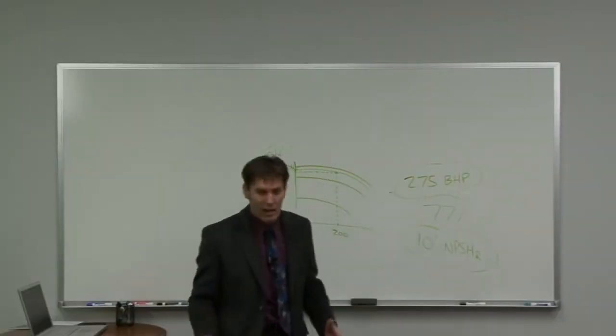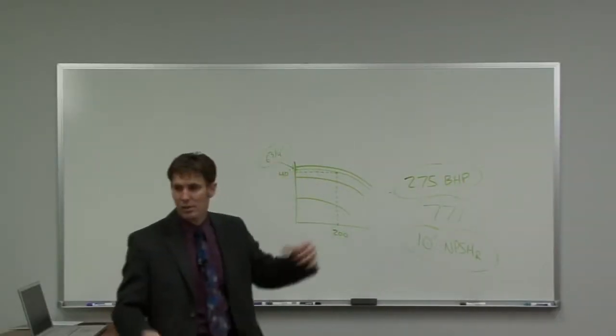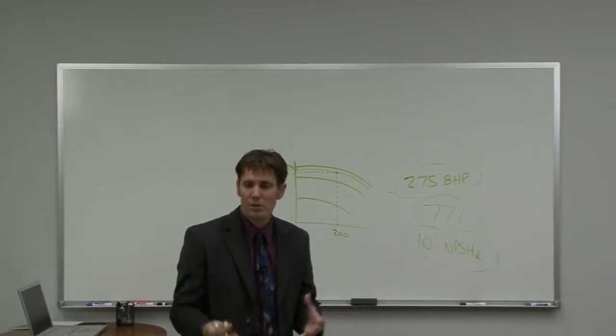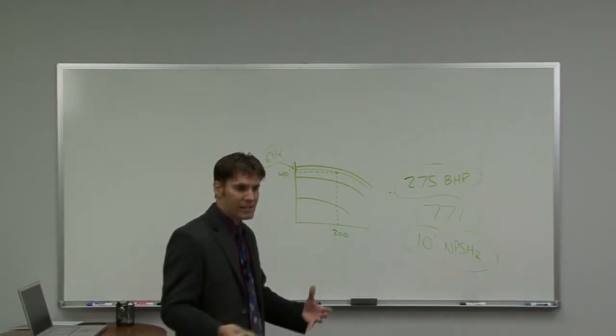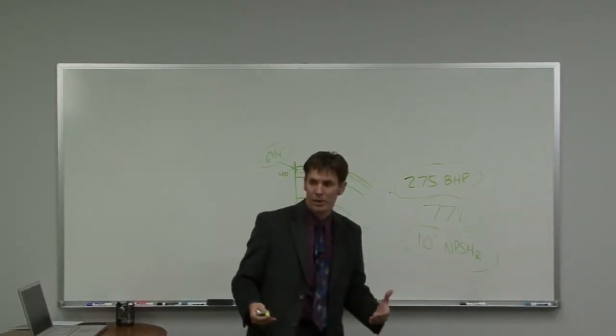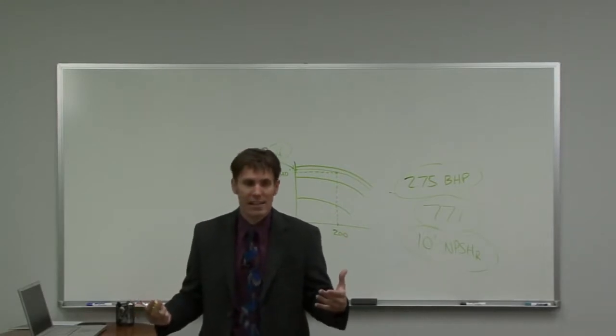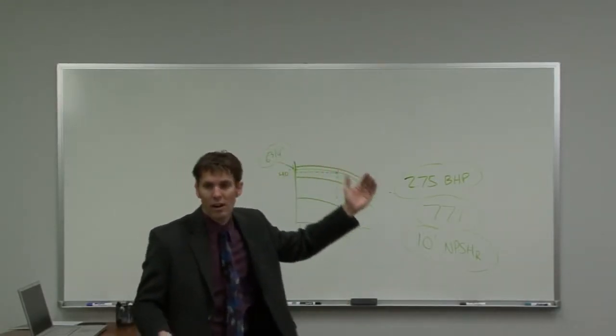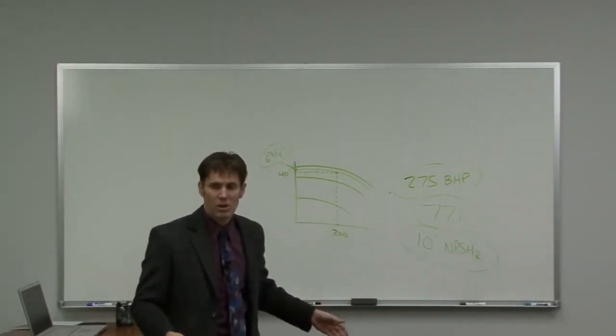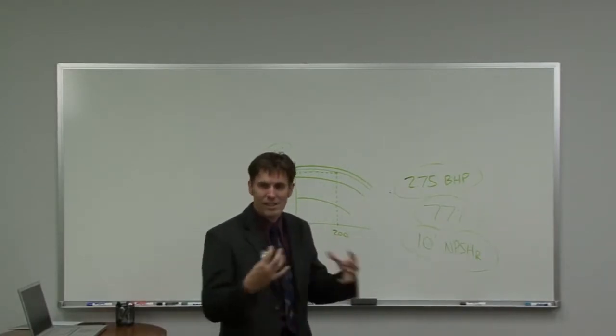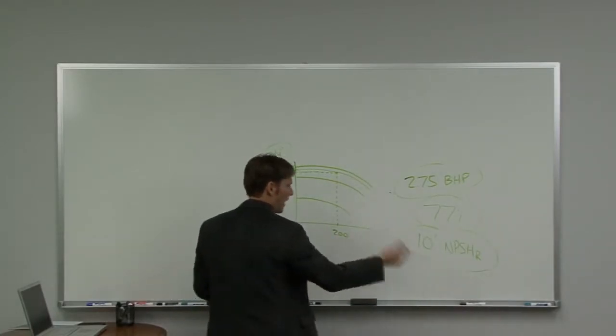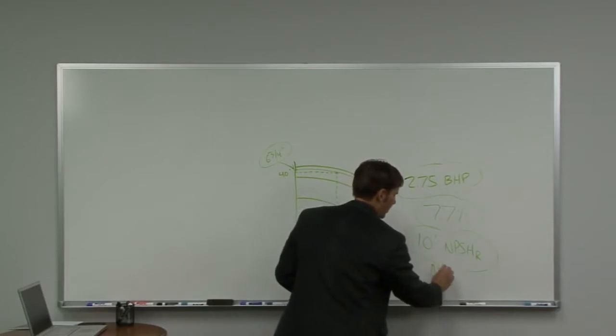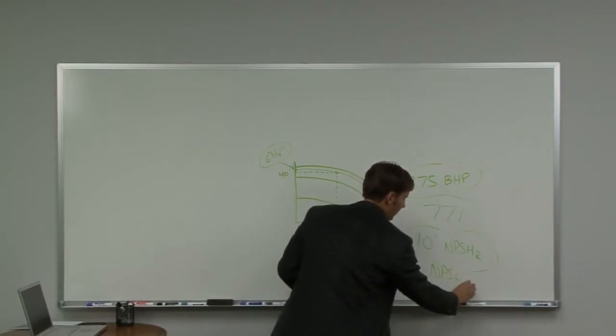Now, I'll tell you this right now. Most closed-loop hydronic systems that are closed to the atmosphere are pressurized to some given pressure, maybe up to 12 psi for a single or 2-story building. When we get into a high-rise, this high-rise might be 20 stories tall, you're going to have a lot more pressure. We're going to have so much pressure in these closed systems that when we calculate our NPSHA, you're going to have so much more suction head available.